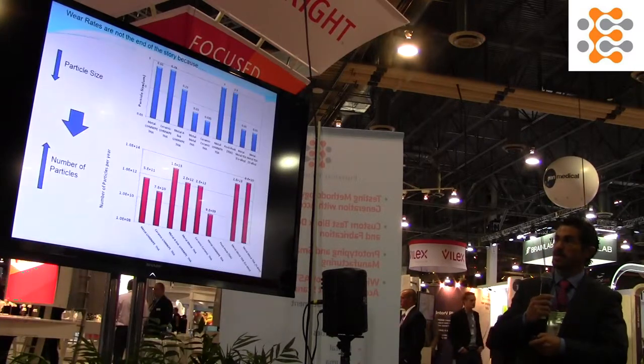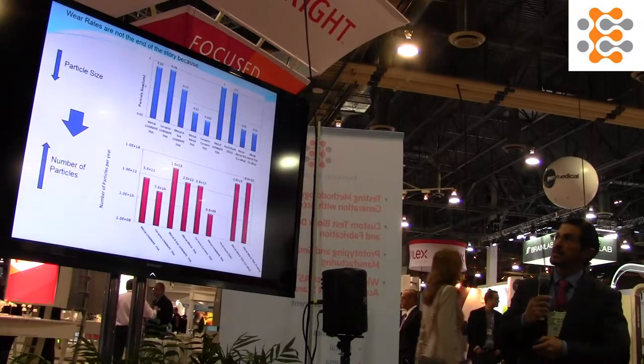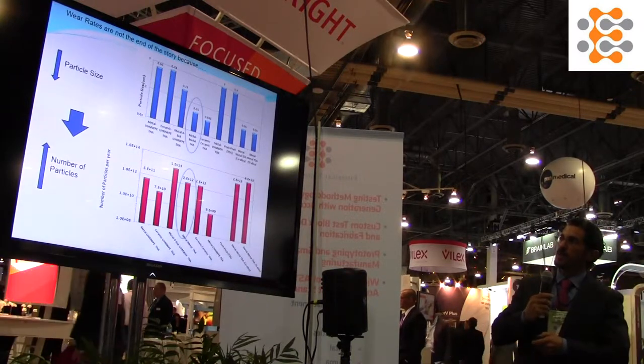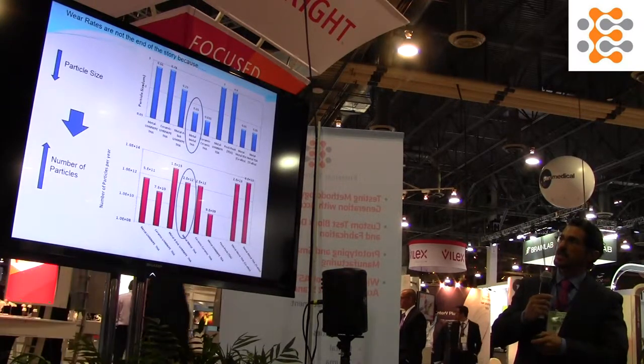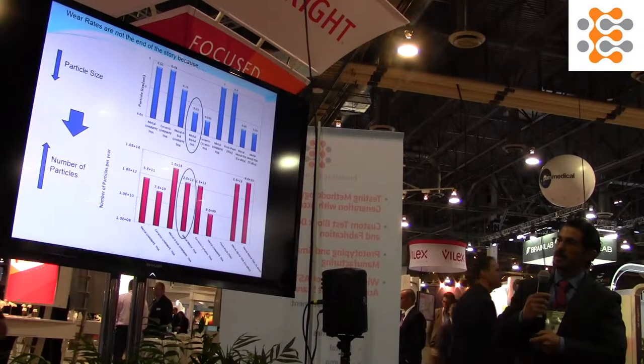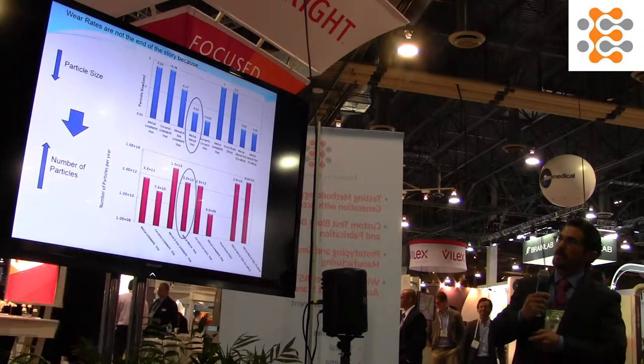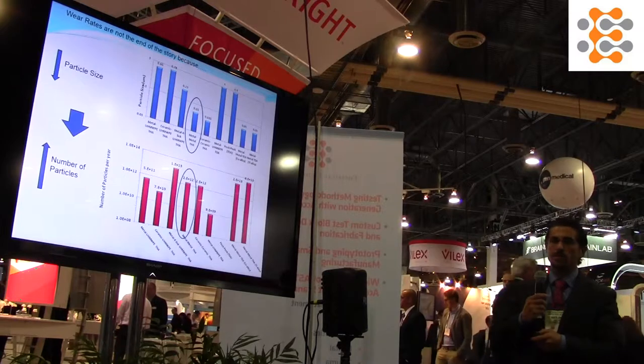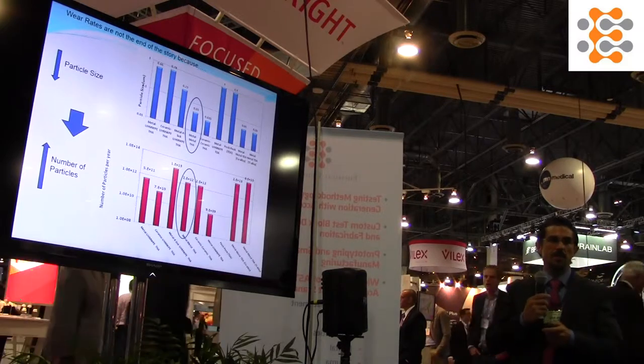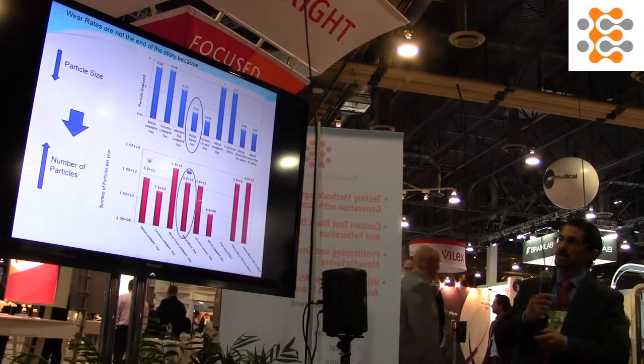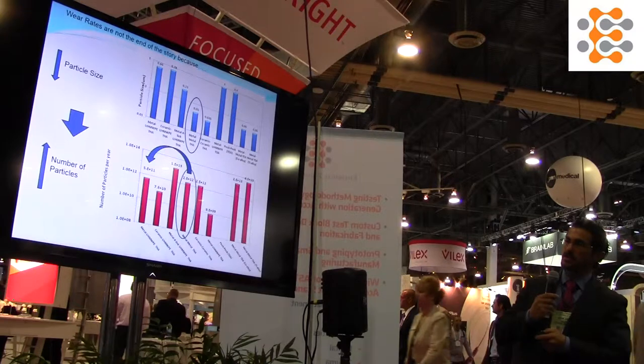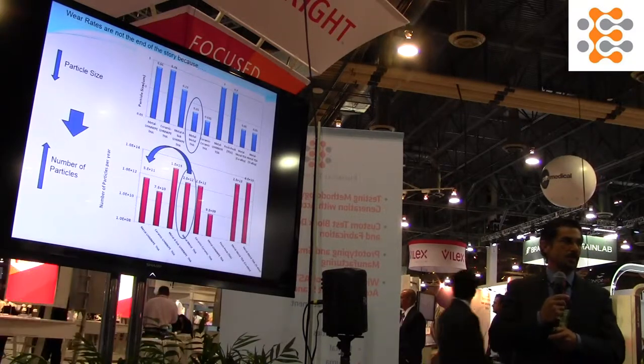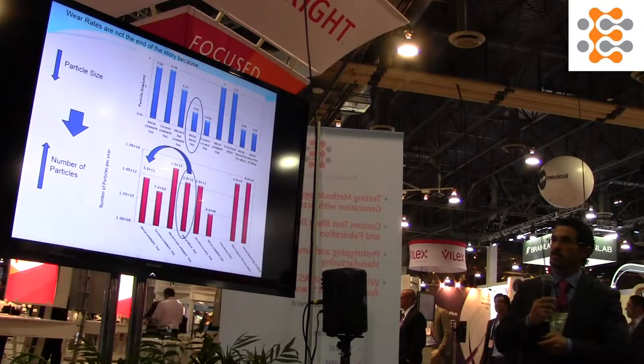Inducing pseudotumors — not much of that anymore. Not only is it the particle size that you can see with metal-on-metal, but it's the number of particles that it creates. It's a particle size and amount of mass loss that actually shows an order of magnitude more particles than metal-on-poly, due to the small size of those metal particles.